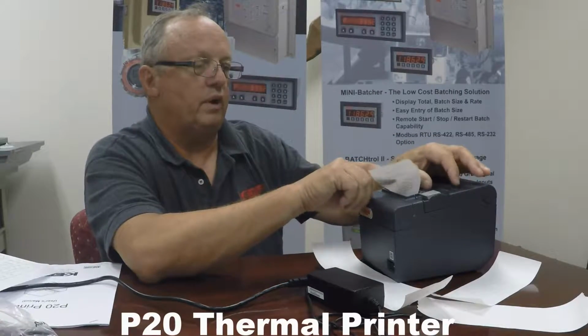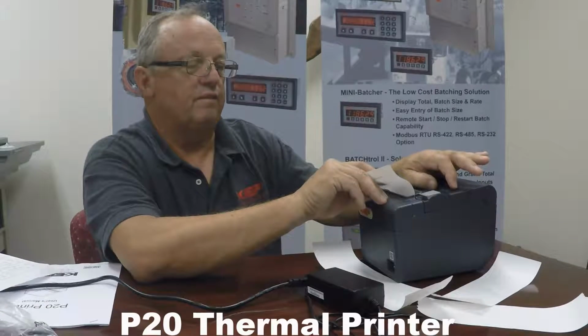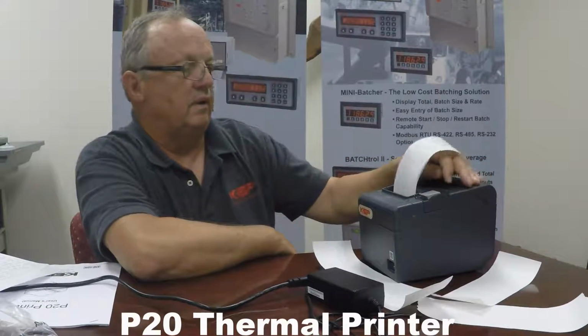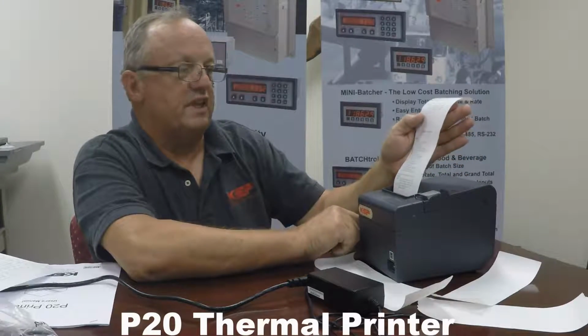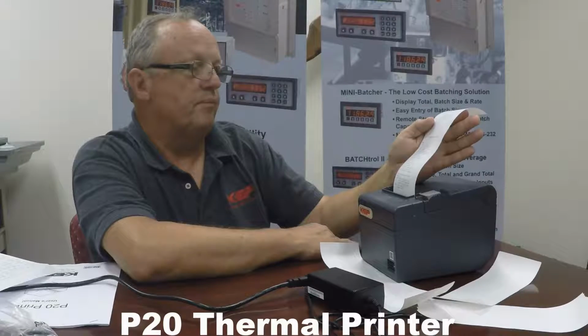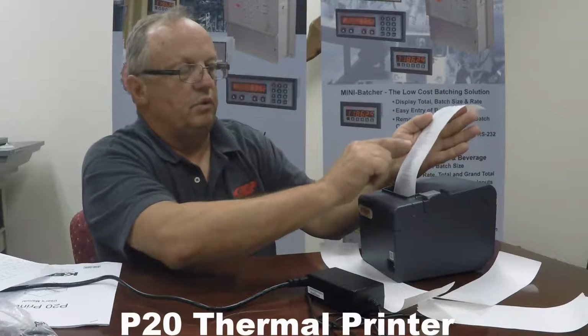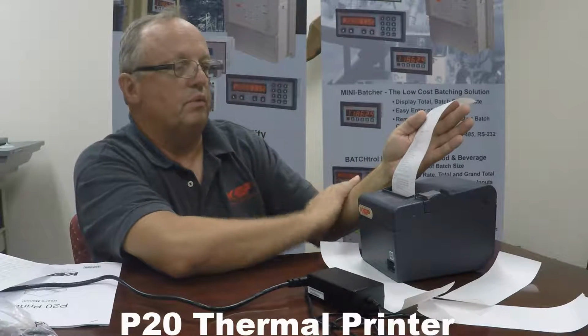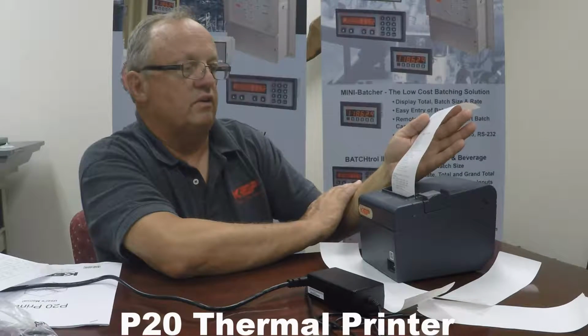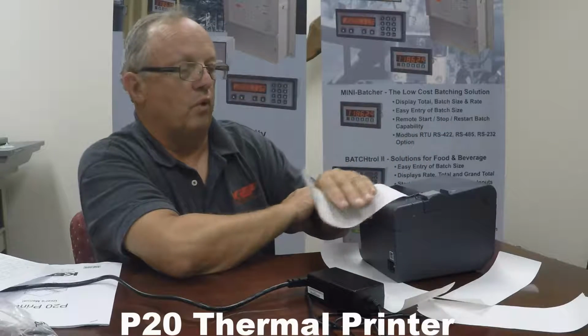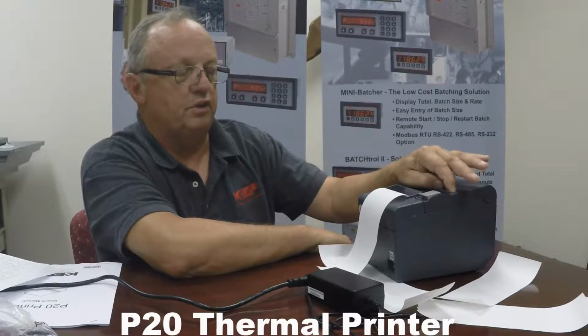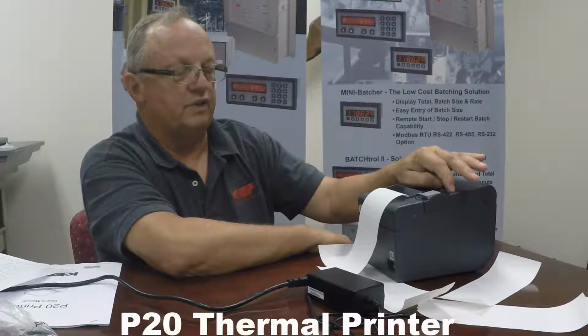Now, I'm going to be interested in something not currently in this unit. So I'm going to go to the Customize Value Settings. This is done by 3 quick depressions, 1, 2, 3, followed by a long depression. Now it's giving me a very extensive list of selections that I can use. And in this case, we're going to be going to the serial interface settings to go through the basic baud rates and other similar settings. So again, since this is selection 4, it'll be 4 quick depressions, 1, 2, 3, 4, followed by a long selection.